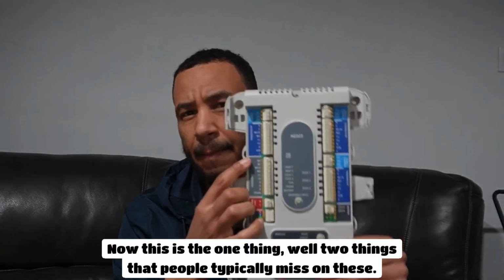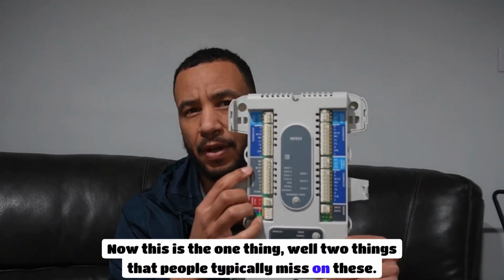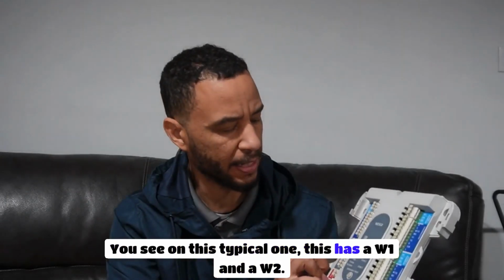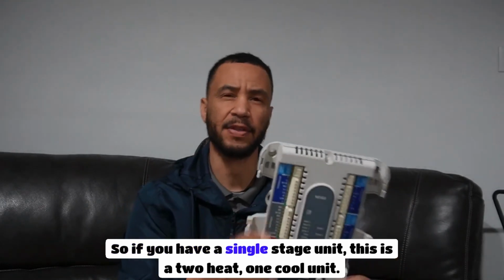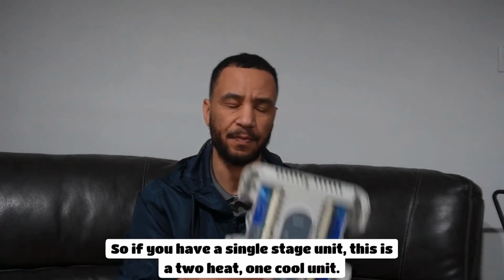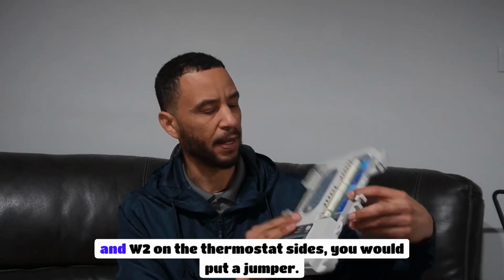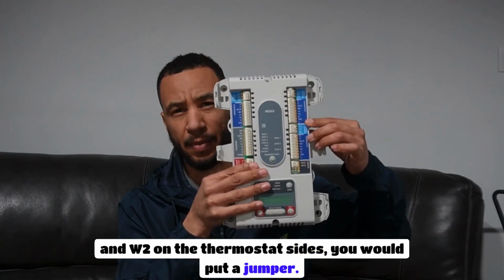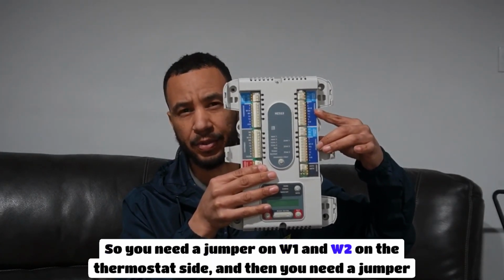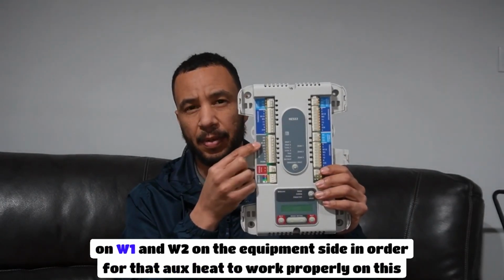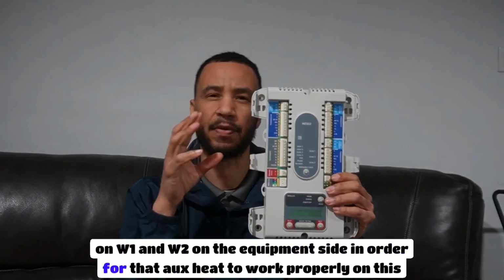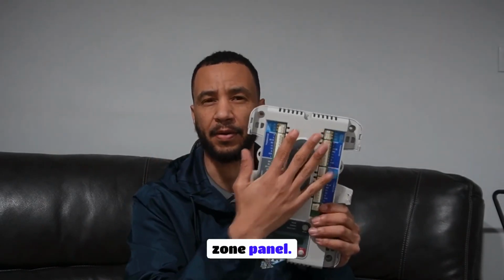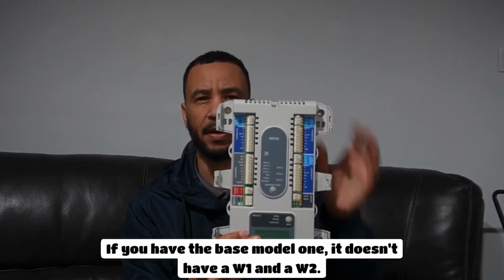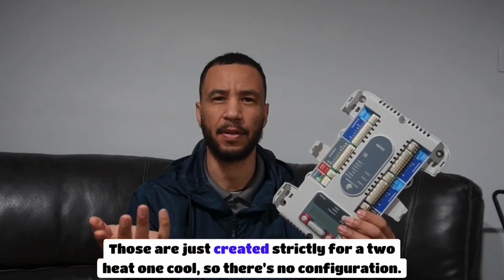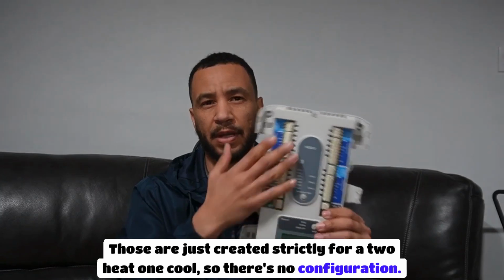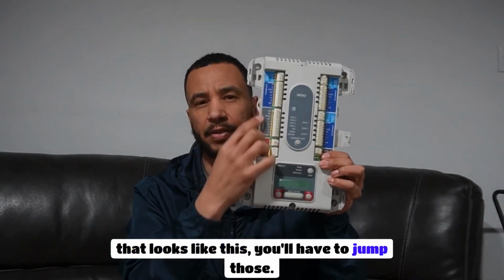Now this is the one thing, well, two things that people typically miss on these. You see on this typical one, this has a W1 and a W2. So if you have a single stage unit, it's just a 2 heat, 1 cool unit. What you'd have to do on the W1 and W2 on the thermostat side is put a jumper. So you need a jumper on W1 and W2 on the thermostat side, and then you need a jumper on W1 and W2 on the equipment side in order for that aux heat to work properly on this zone panel. If you have the base model one, it doesn't have a W1 and a W2. Those are just created strictly for a 2 heat, 1 cool, so there's no configuration. But if you're using this one here that looks like this, you'll have to jump those.